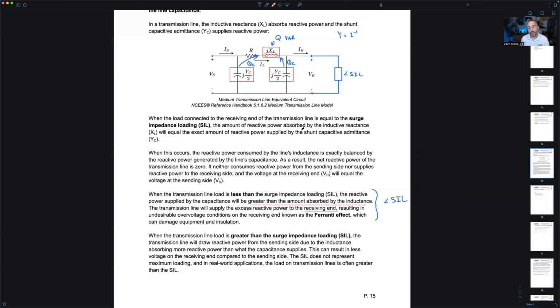The amount of reactive power absorbed by the inductive reactance of those transmission line capacitors is less than the total amount of reactive power being supplied by the shunt admittance. So now we've got some excess reactive power, Q in units of VARs, being sent to the receiving side.